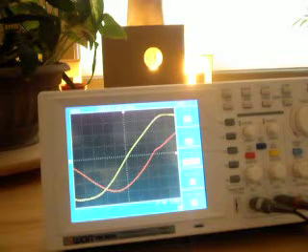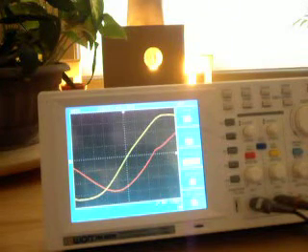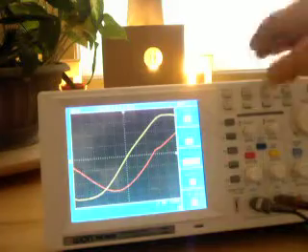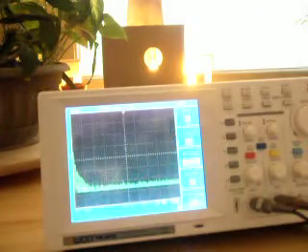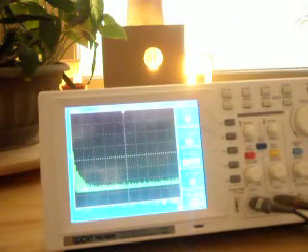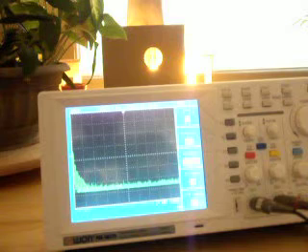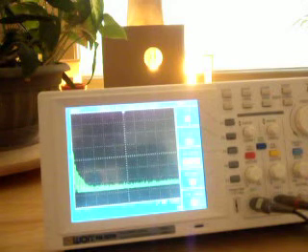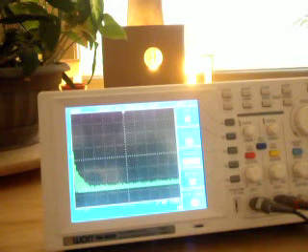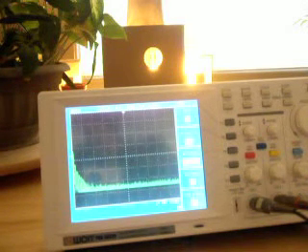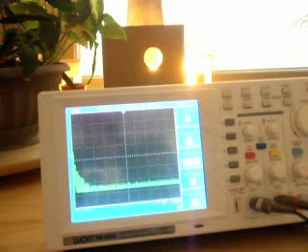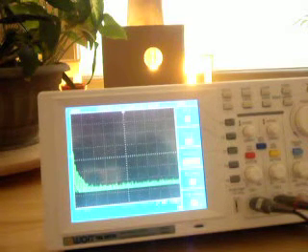I'm going to switch on the harmonic function, which is called a fast Fourier transform function, and we can see those harmonics over on the left. What you'll see all the way along the timeline is a flickering waveform, and that generally indicates there's electrical noise on the system.